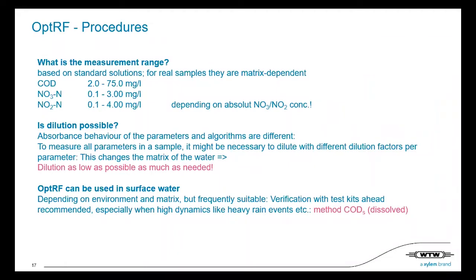What measuring range can we do? It's based on standard solutions, and as I said, we are measuring real samples. Depending on the user calibration, the absolute measuring range can differ a little, but based on standard solutions we are in the range between 2 and 75 milligrams per liter COD.